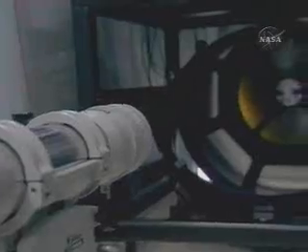And so what we're looking for is to contain the photons in as small a circle as possible. The better the focus, the more photons will arrive onto the XRS. So the process is done again in optical and white light by putting the four quadrants on the ring and then looking at where each quadrant projects its image and adjusting these until they all project to the same spot.